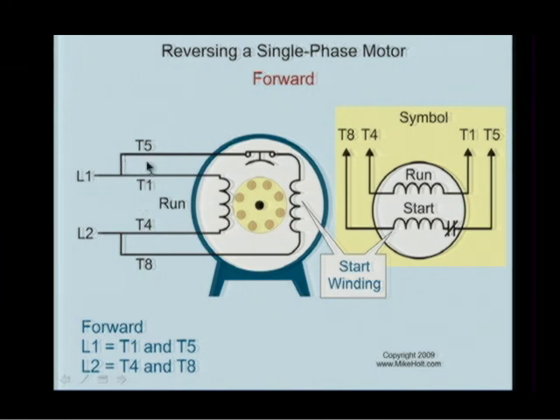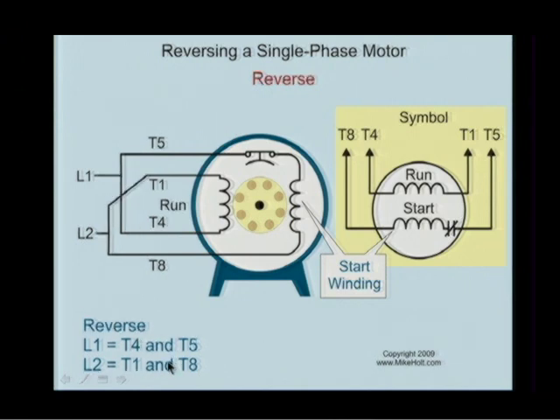Gotcha. So it'll say take T1 and T5, tie them together with a wire nut, and connect to line 1. Take T4 and T8, tie them together, that's going to get line 2. If we do that physically, then this motor is going to have, let's say, a clockwise rotation, a positive rotation. Everybody with me there? Okay. And then here are the notes: forward, that's what you do. Then the instruction would say, if you take T5 and connect it to T4, I'll look at how the windings connect in a while, to line 1, and T1 and T8 to line 2, so 4 and 5, 1 and 8. That's going to be the reverse.